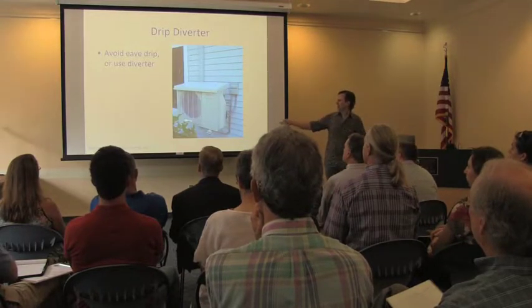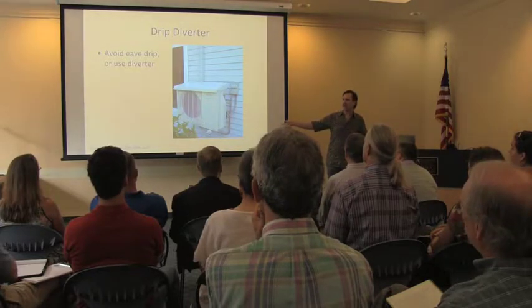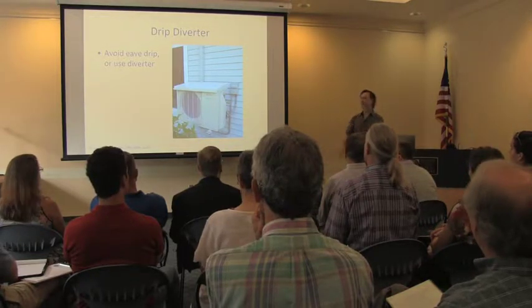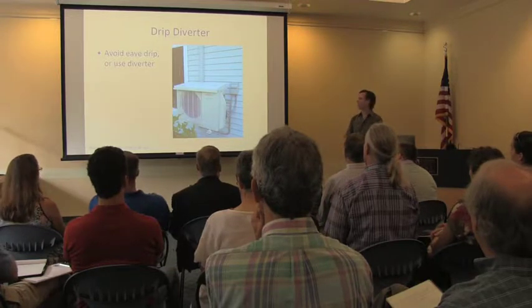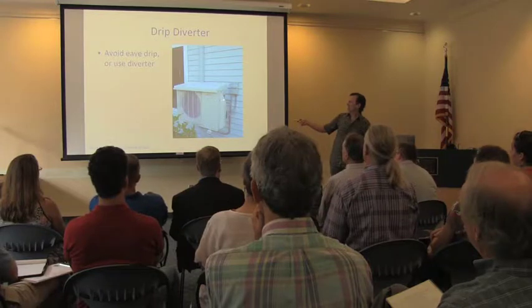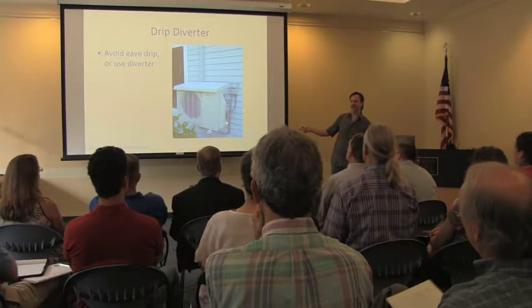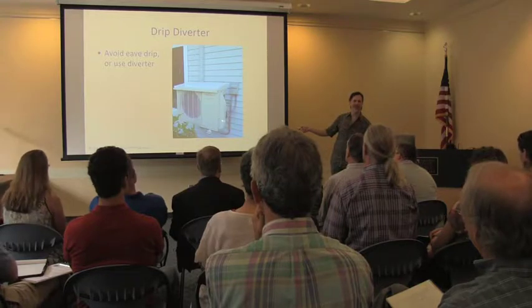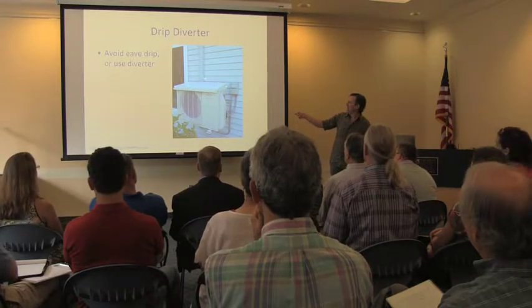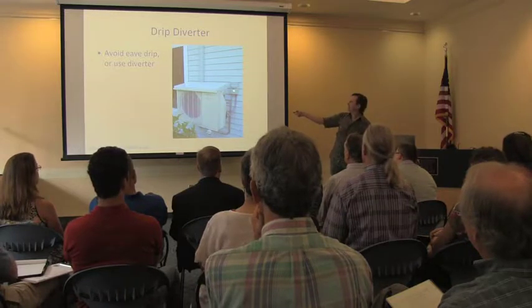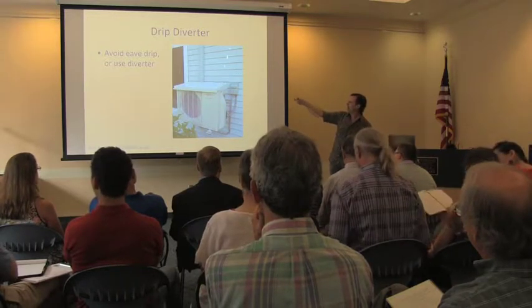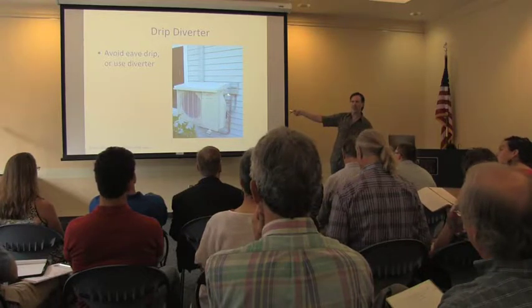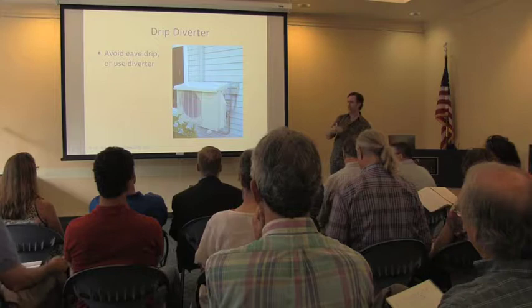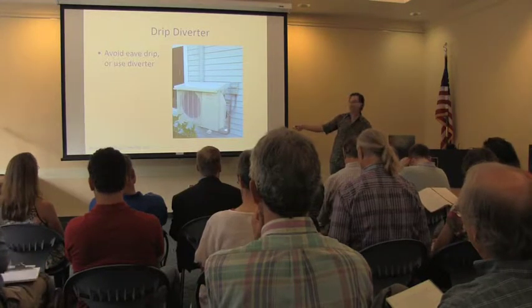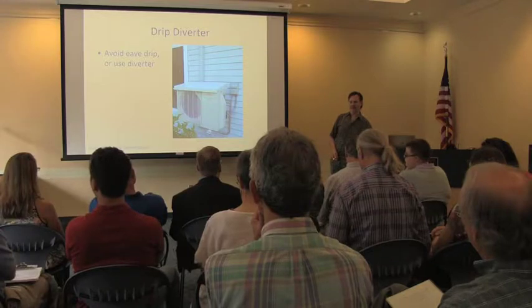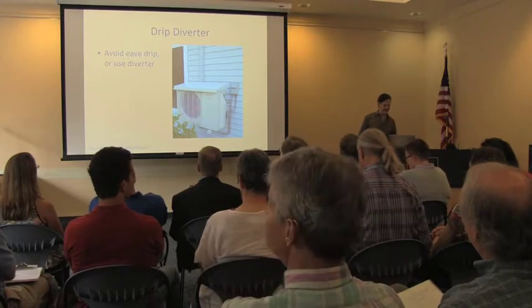Some of these units have what's called a drain heater or pan heater for cold weather. When they defrost, the moisture that's coming off of that coil drips down in the bottom. And what we've found is that even in very cold climates in Maine, they're installing something like 400 of these a month on average for the last 3 or 4 years in Maine. And as long as you can keep them away from eaves, or if they are under an area where you can't avoid dripping off the roof, you have a drip diverter over the top of it like this. And so as long as it's not getting extra moisture from above, they really don't need the pan heaters, and they can operate very, very well without that extra energy load.